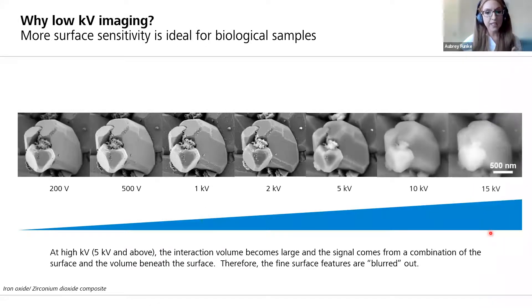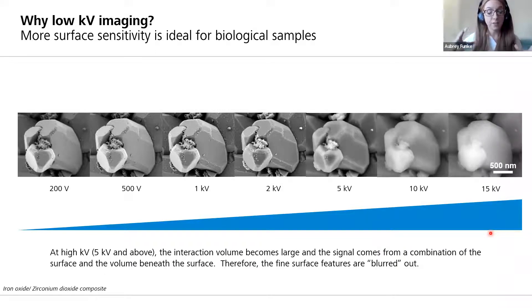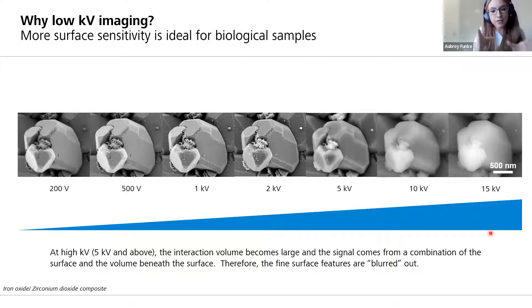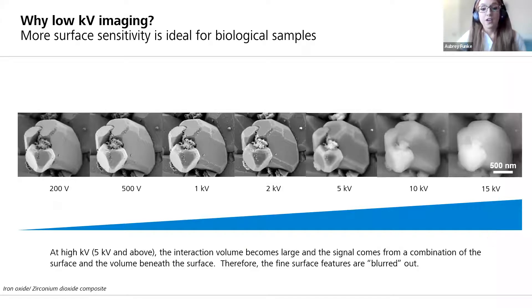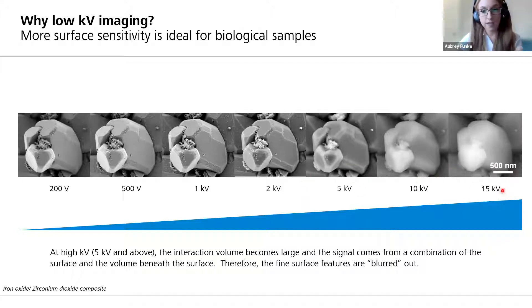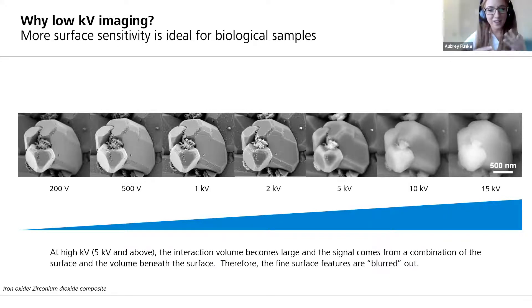For different accelerating voltages, the different interaction volumes result in a really different type of image being generated. I recommend adjusting that accelerating voltage and choosing the best voltage that gives you the most highly resolved, sensitive area of those really finite surfaces of that sample. At lower kVs, the images show better definition of surface features, and at higher kVs — starting at 5 kV and above — you're starting to get a combination of the surface sample and the area below it.